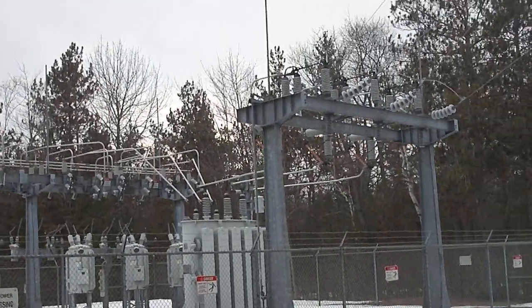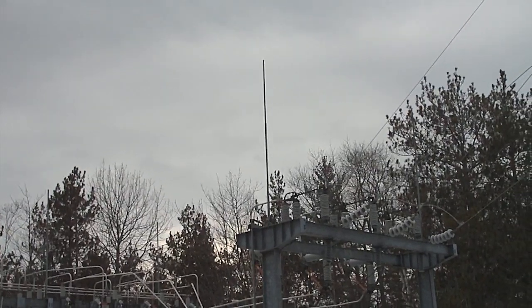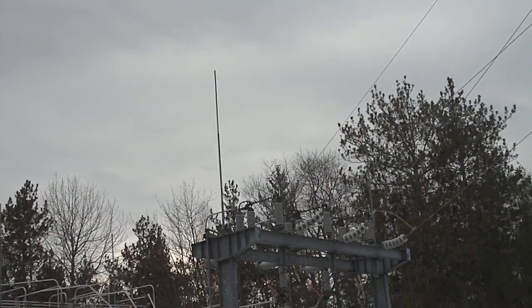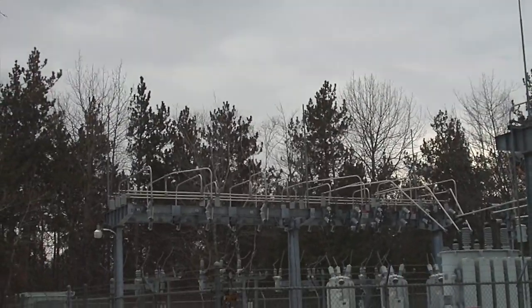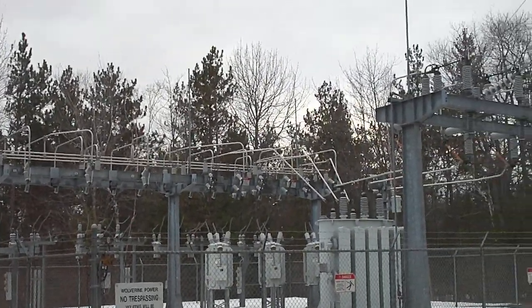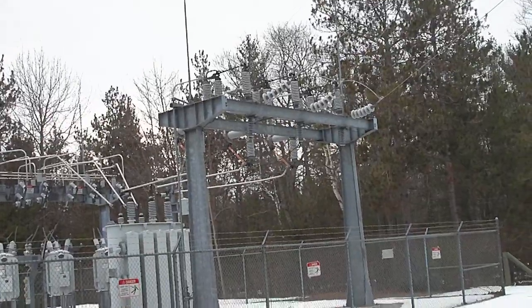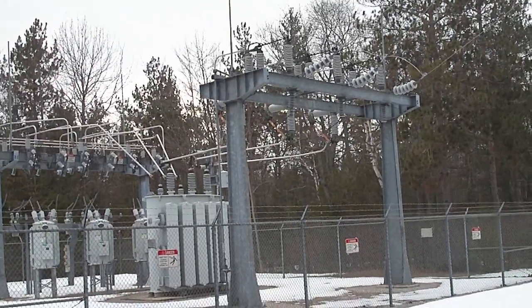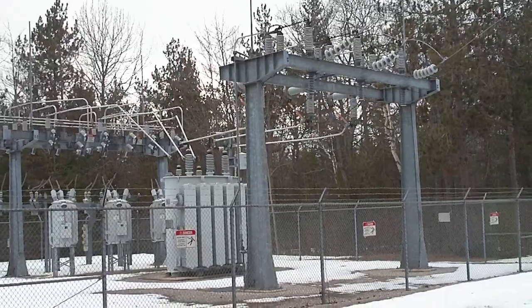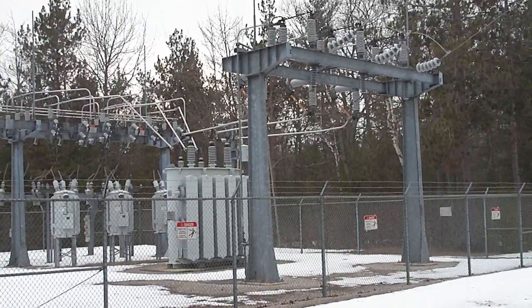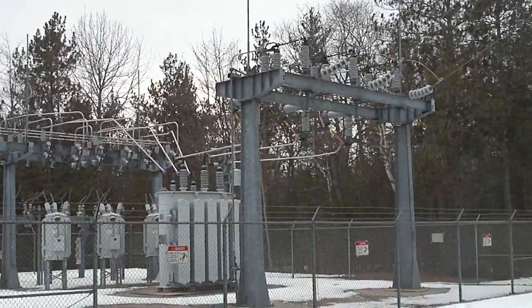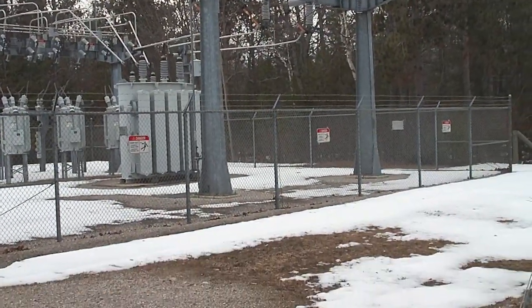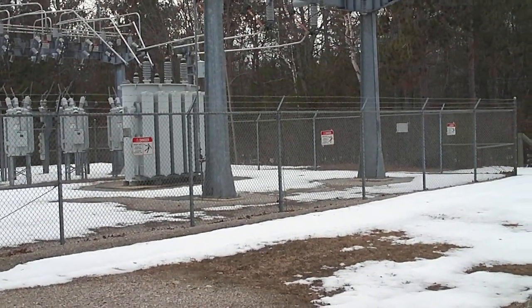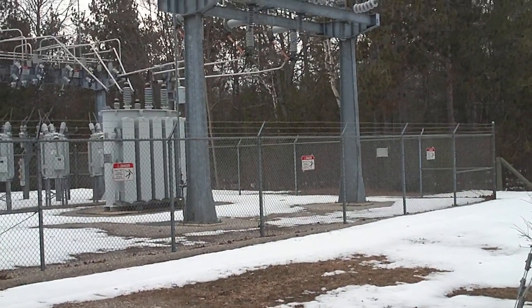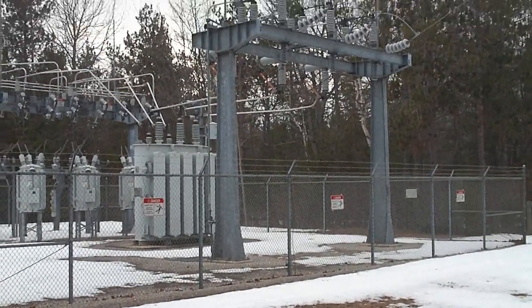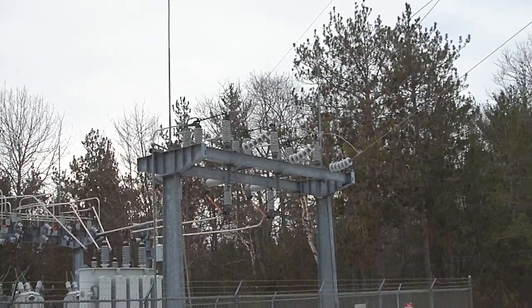Another thing I want to show you is if you look up top, you'll see these lightning rods on top of the superstructure. You'll see them pretty much all over. Sometimes they have little baskets on top. These are just lightning rods by themselves. There's two schools of thought on lightning rods for protection. One is that it gives the lightning an actual place to strike, with a nice braided 4/0 ground wire going down to the grounding grid. Other people believe that it actually bleeds off the static electricity, so the lightning doesn't even strike it.